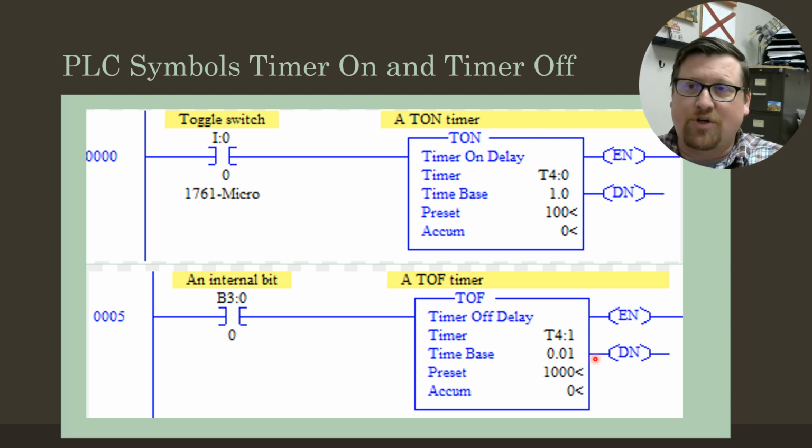Like I said, this is going to depend on which PLC you've got. Some PLCs, the timers can count to a higher number, and so you don't have to be as concerned with that as you do in the SLC 500s. But the reason you're concerned about that to begin with is how critical it is if you're counting by ones or counting in hundredths of a second. Is it something critical where you need to check that timer every tenth of a second, or is once a second good enough?